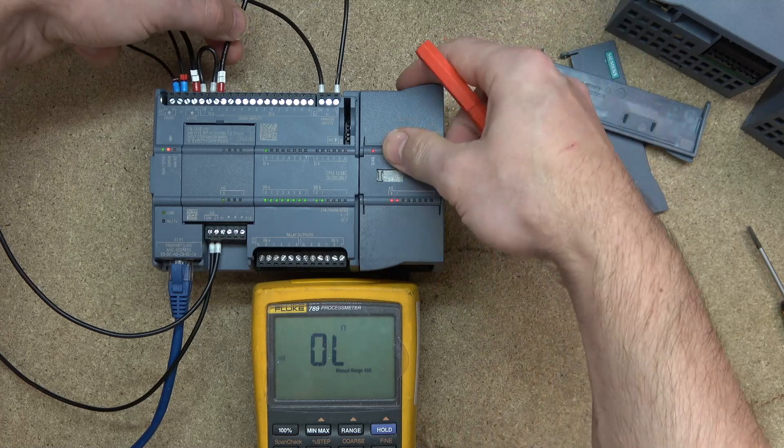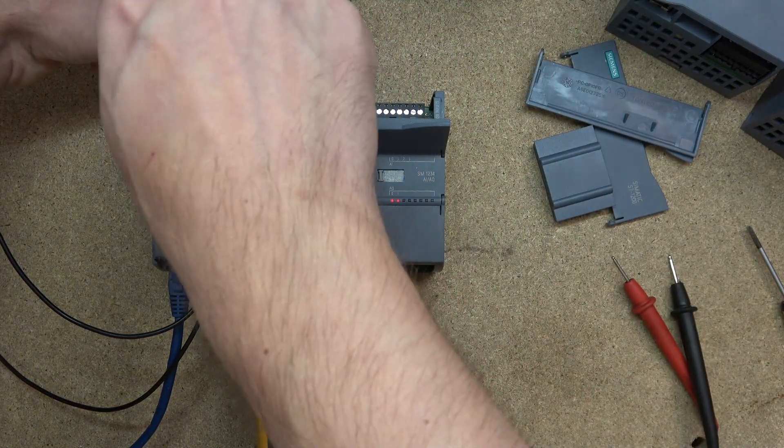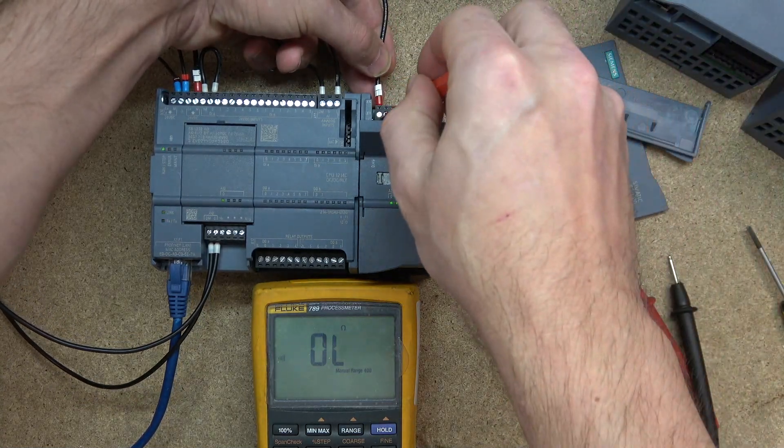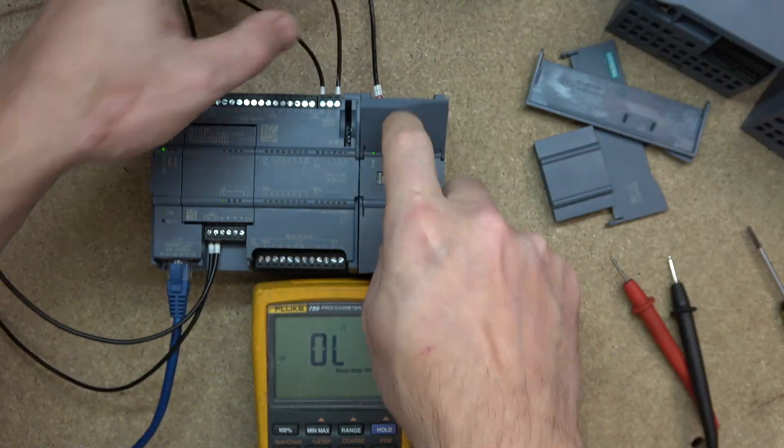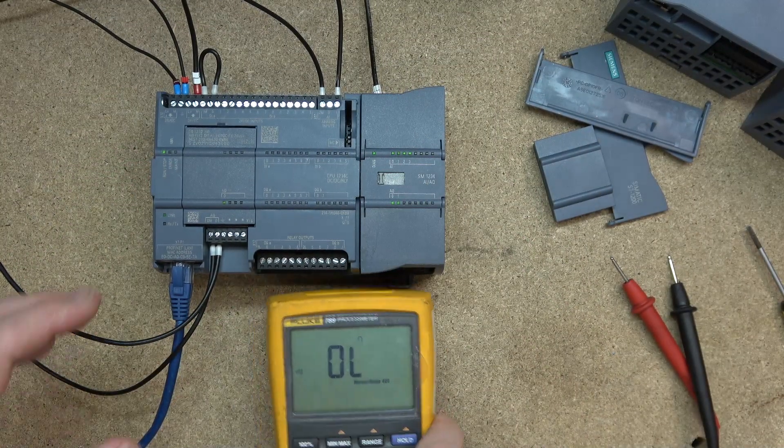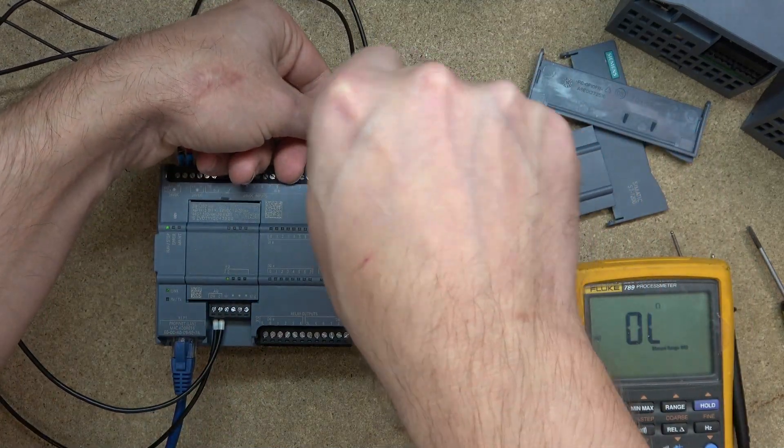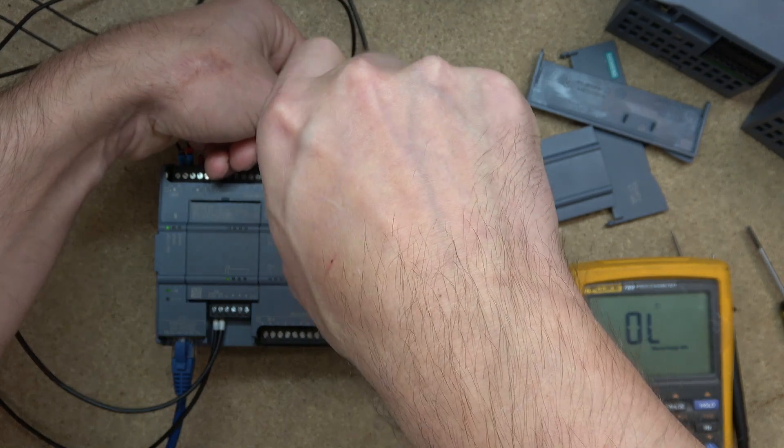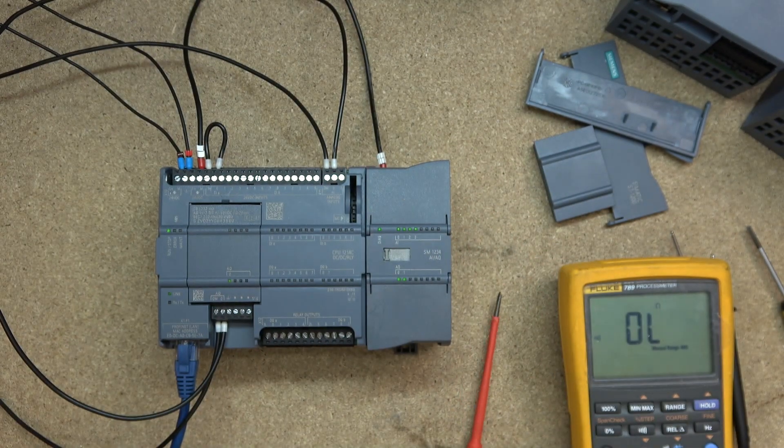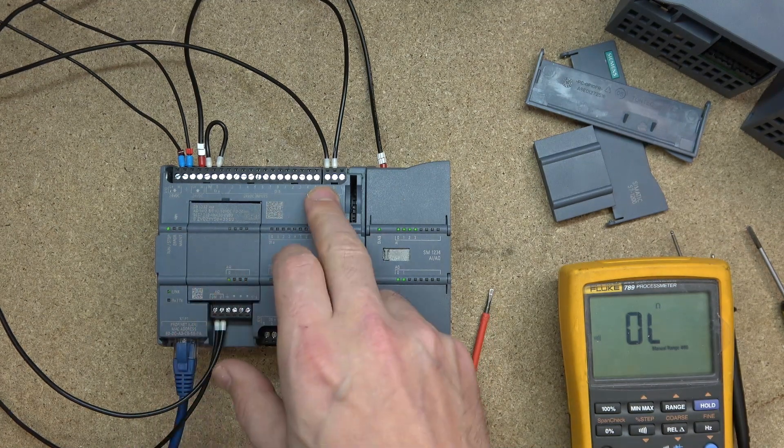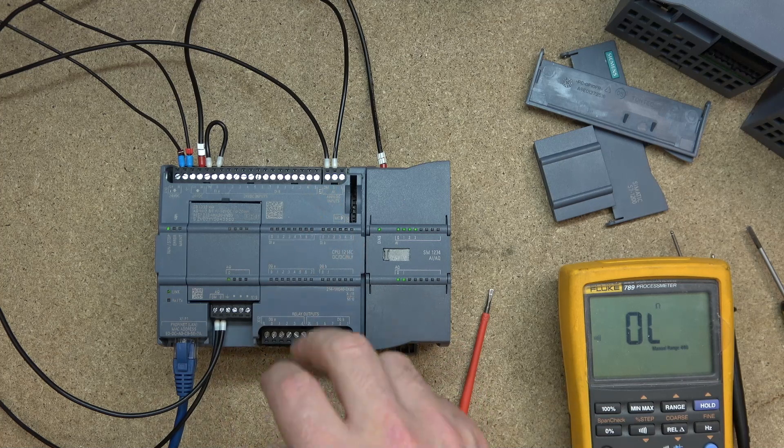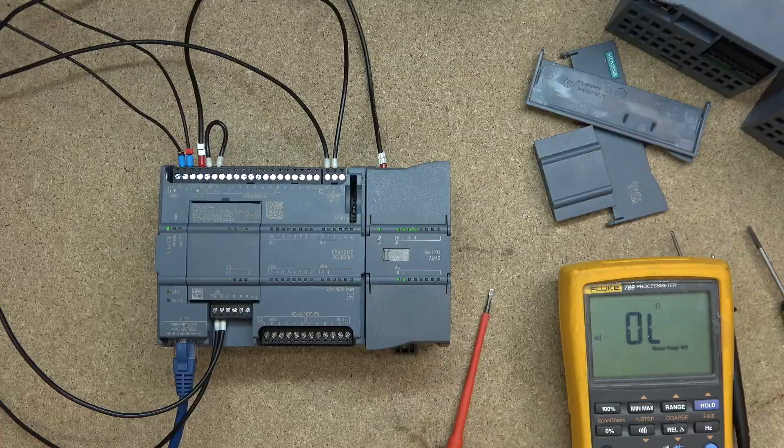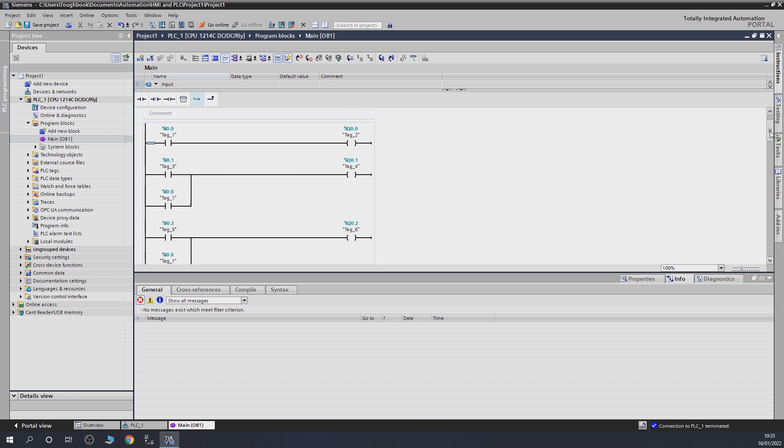And it looks like all the relay outputs are healthy and working absolutely fine. So that flash, that red flashing is really annoying me. So I just take that one in there and move it in here. So it stops flashing. So basically that's if you got power missing from your cards, it will start flashing red. Next up, next up, we are going to be checking, let's start actually with the first channel in here, our analog input one. So we're going to be outputting voltage from here into the analog input one. We should be getting a pretty solid reading into these analog inputs when the analog output is sending out. So let's jump back on our laptop again. Sorry guys, I'm still messing around with my cameras. Still can't seem to get it right.